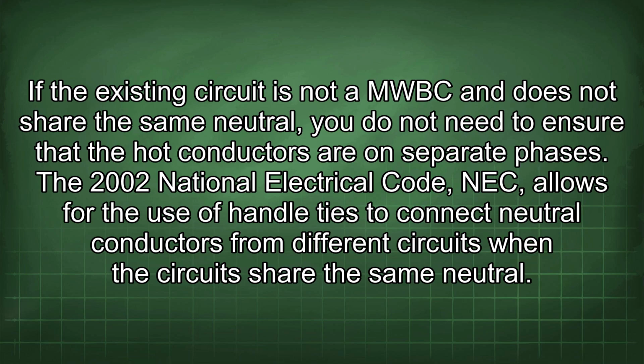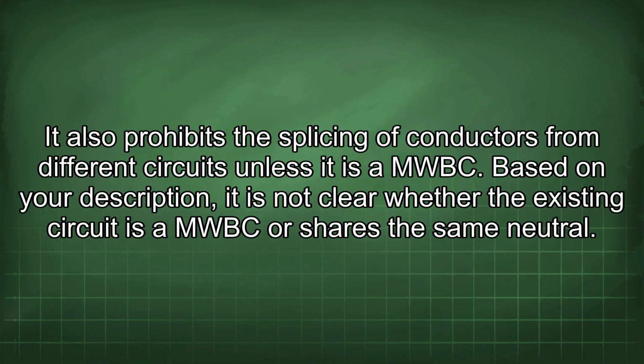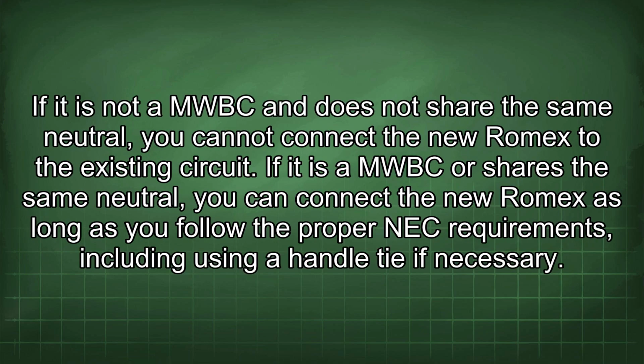The 2002 National Electrical Code, NEC, allows for the use of handle ties to connect neutral conductors from different circuits when the circuits share the same neutral. It also prohibits the splicing of conductors from different circuits unless it is MWBC. Based on your description, it is not clear whether the existing circuit is a MWBC or shares the same neutral. If it is not MWBC and does not share the same neutral, you cannot connect the new Romex to the existing circuit. If it is a MWBC or shares the same neutral, you can connect the new Romex as long as you follow the proper NEC requirements, including using a handle tie if necessary.